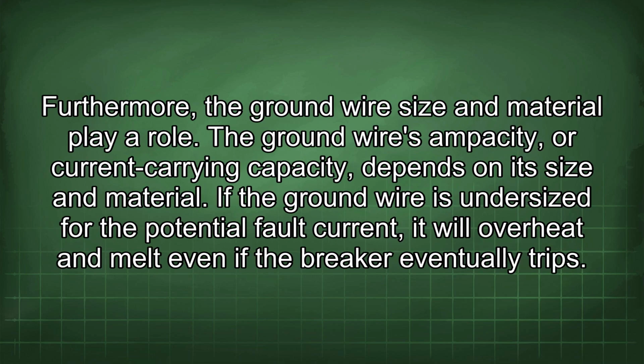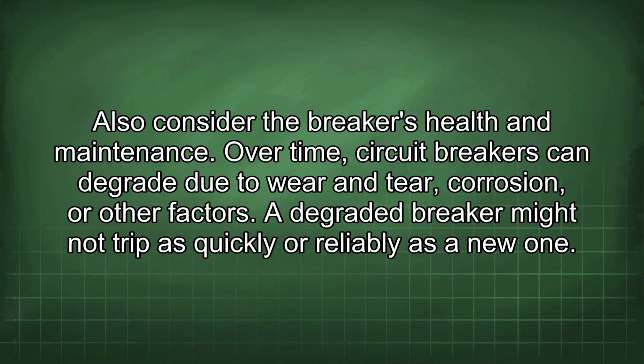Furthermore, the ground wire size and material play a role. The ground wire's ampacity, or current carrying capacity, depends on its size and material. If the ground wire is undersized for the potential fault current, it will overheat and melt even if the breaker eventually trips. Also consider the breaker's health and maintenance.